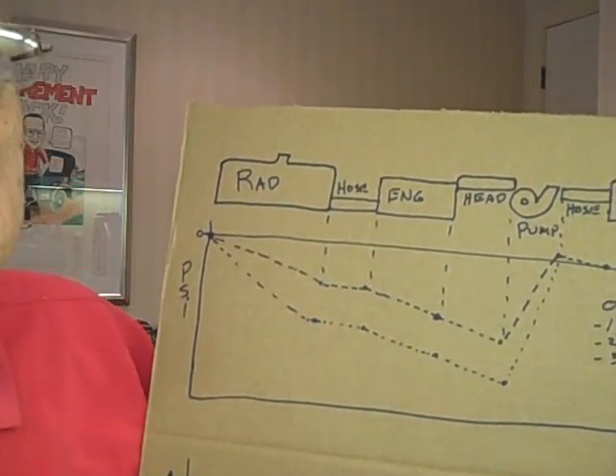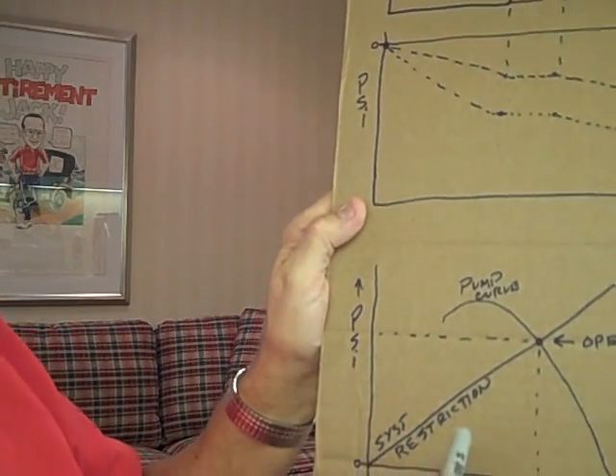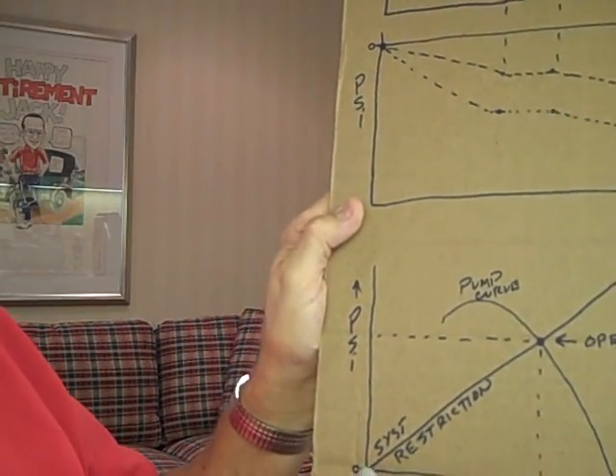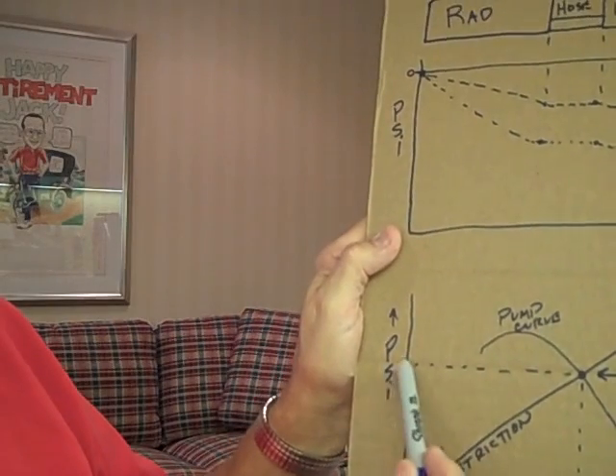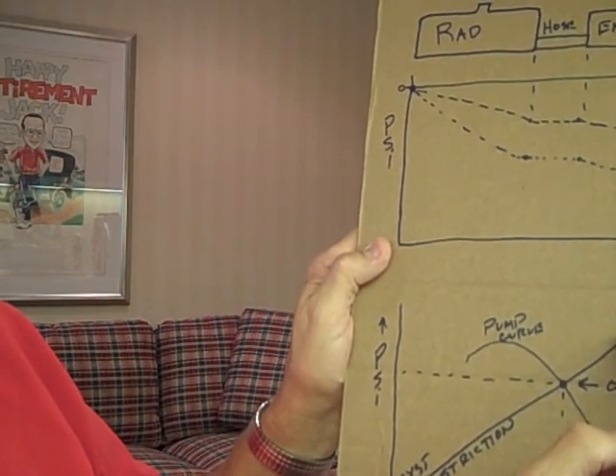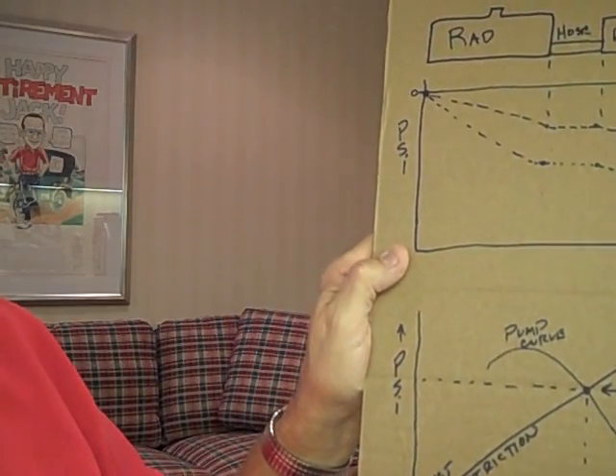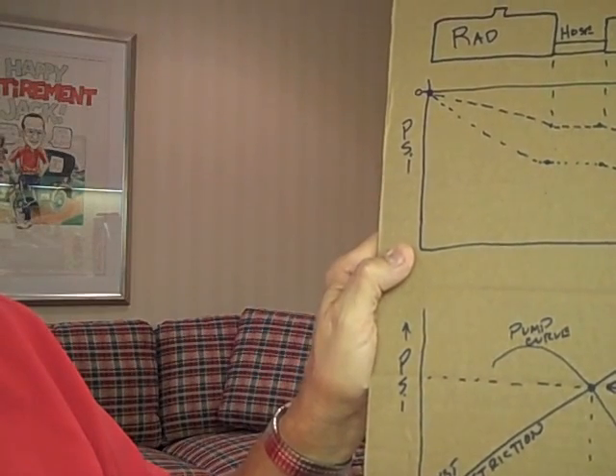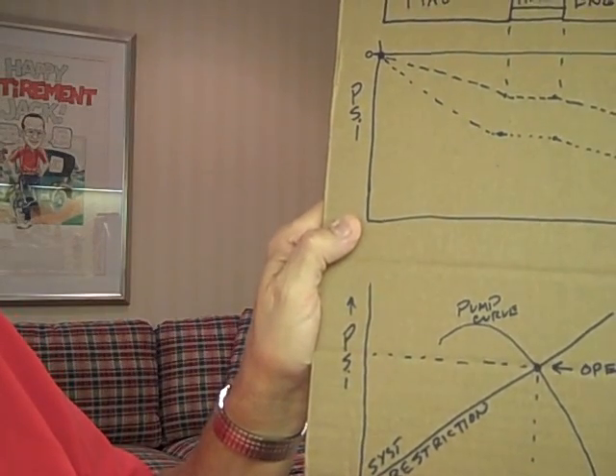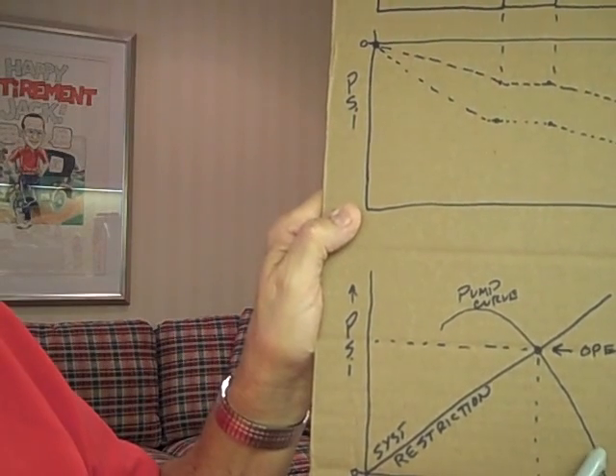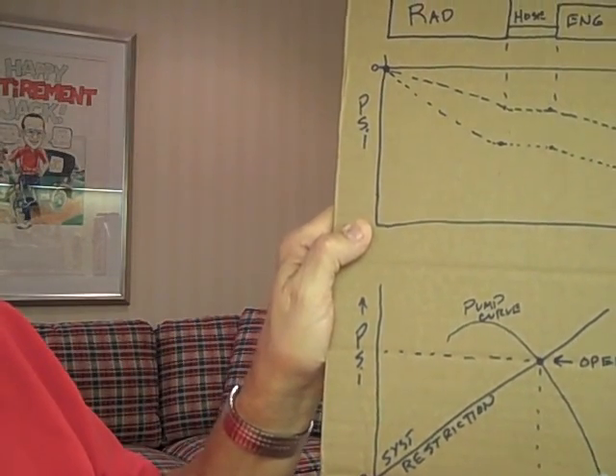I've got a chart here showing pressure and flow. This is a system restriction curve. If you push a lot of water through the radiator, there's a lot of flow. You can plot that and get a system restriction curve. Then you do a pump curve. As you pinch off the outlet, you reduce the flow and the pressure goes up. Every system has a pump curve at a certain rpm and a restriction curve.